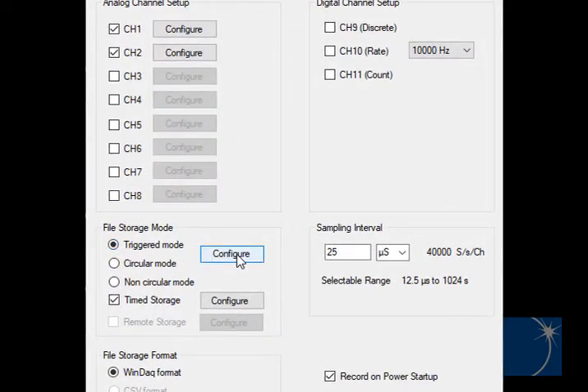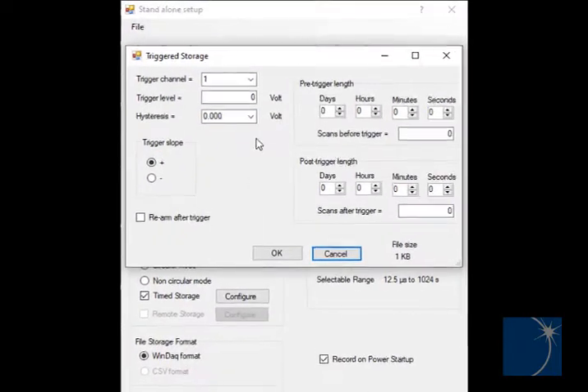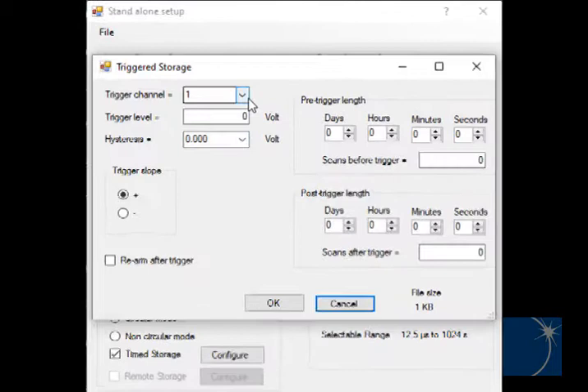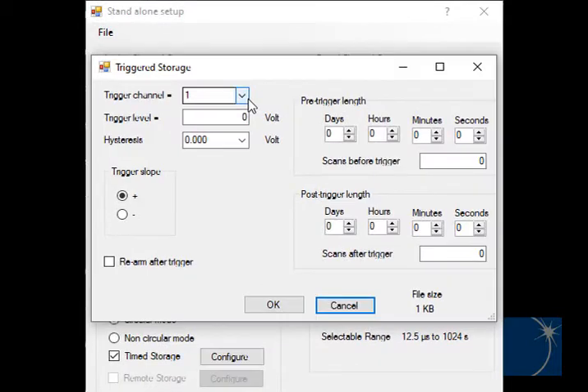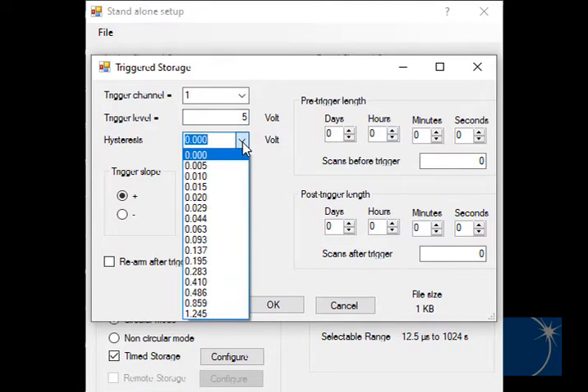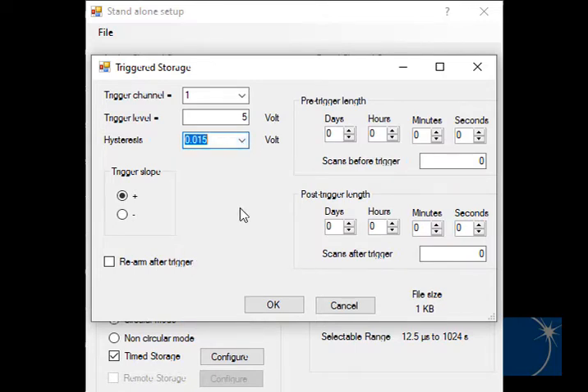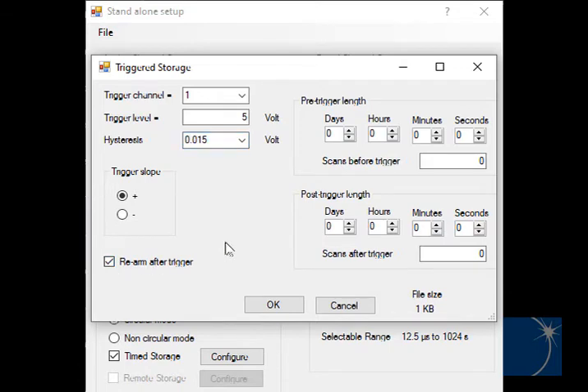Triggered mode allows you to choose a trigger channel, the level on that channel at which to begin recording, a hysteresis, or how close to the actual trigger level you want to start recording within 2 mV, 5 mV, and so forth, a trigger slope, record on the positive going or negative going side of the signal, and rearm the trigger once it's been reached.